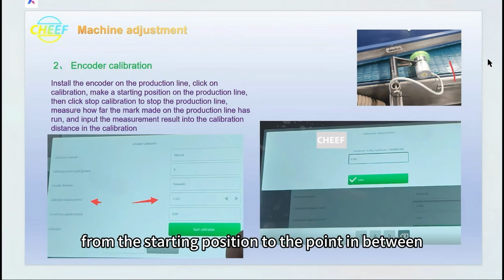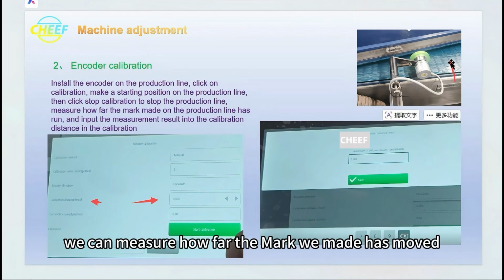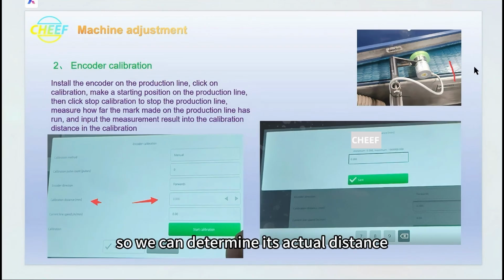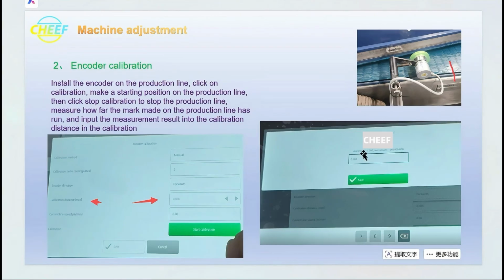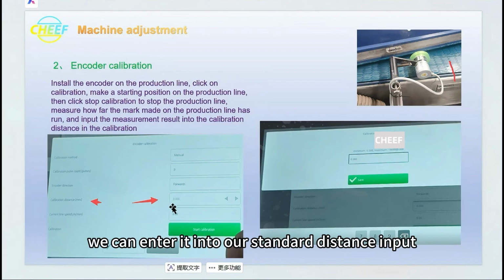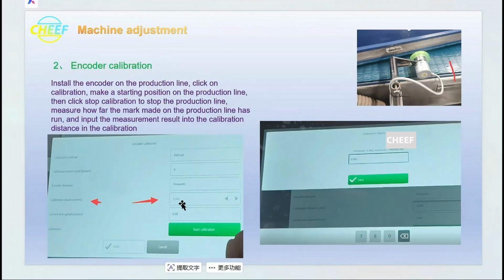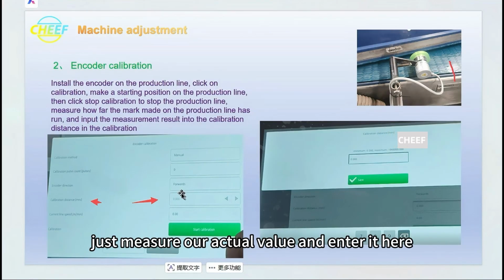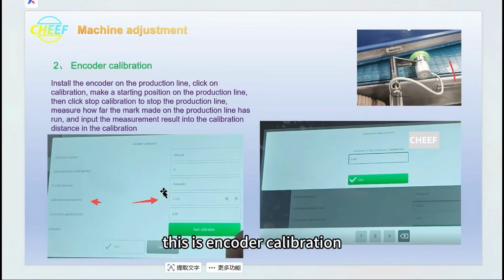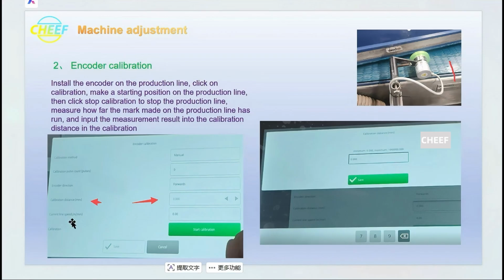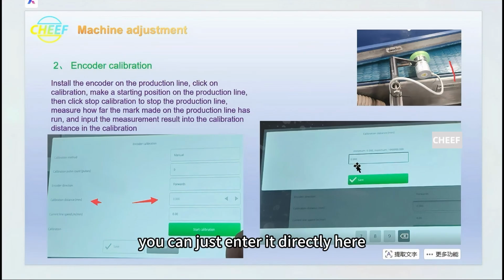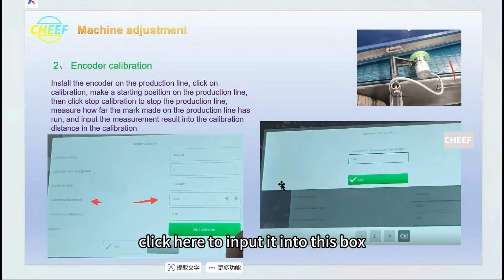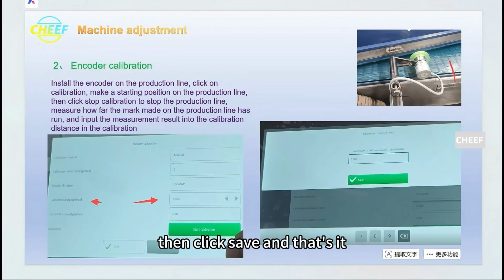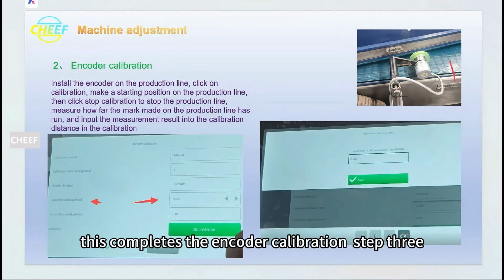In this way, from the starting position to the stopping point, we can measure how far the mark we made has moved, so we can determine its actual distance. After obtaining this actual distance, we enter it into our standard distance input. Just measure the actual value and enter it here. That's all you need to do. This is encoder calibration. Click here to input it into this box, then click save, and that's it. This completes the encoder calibration.